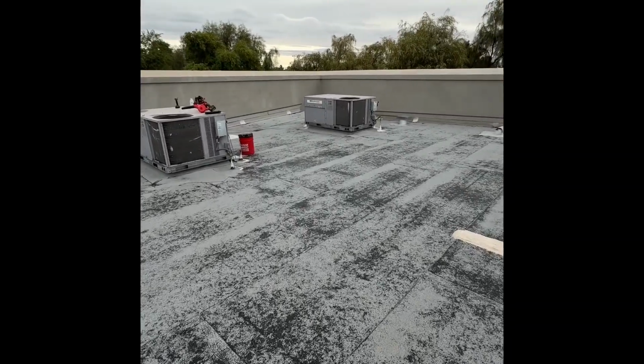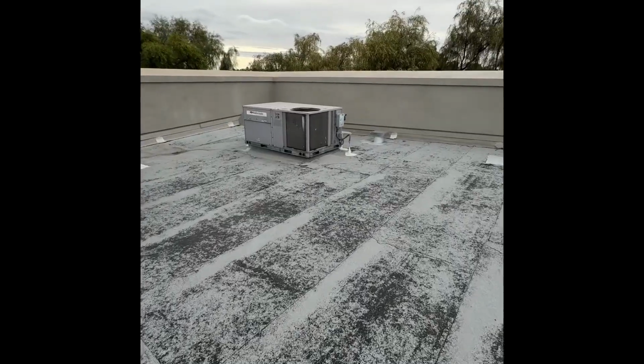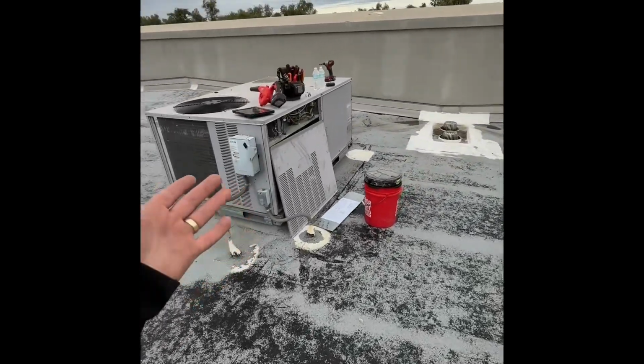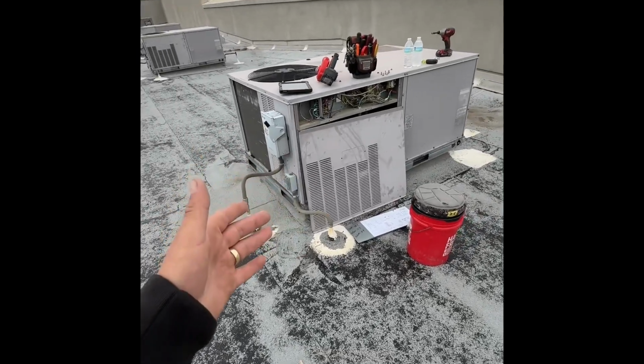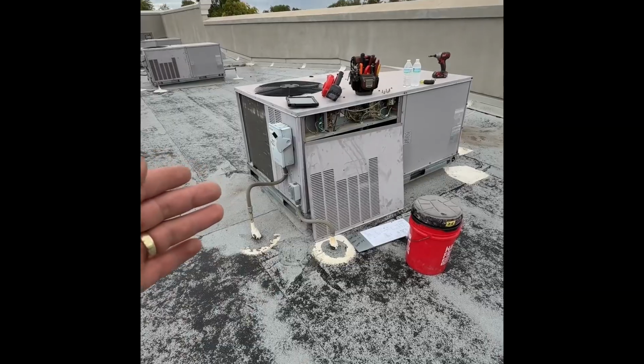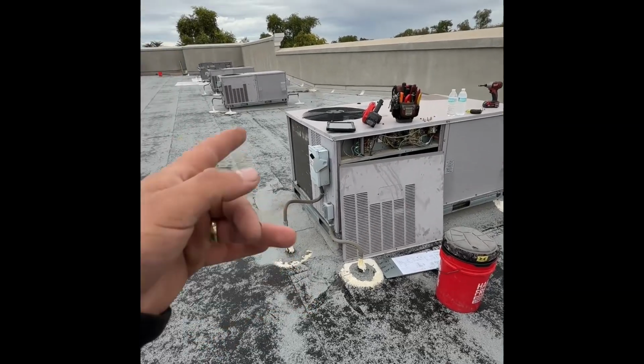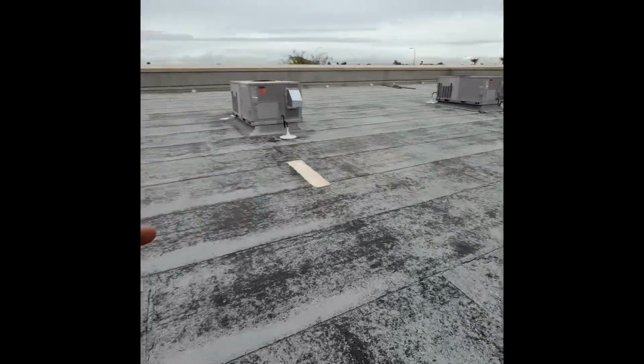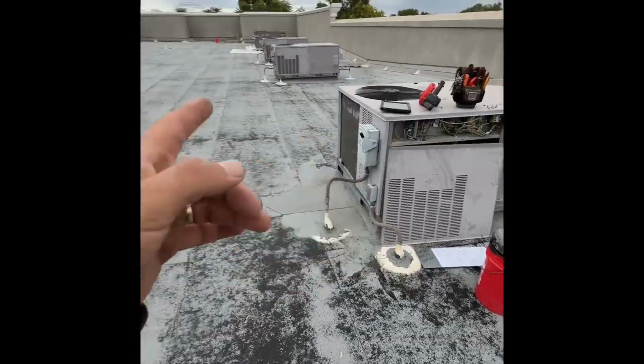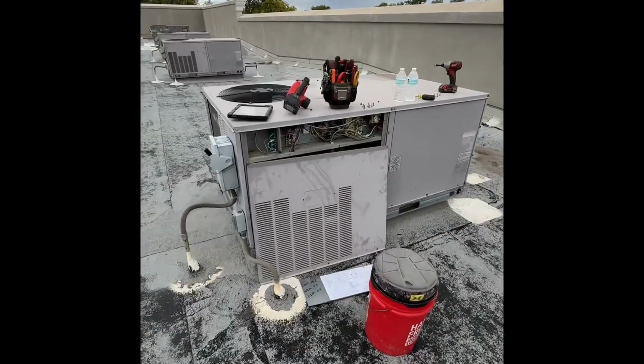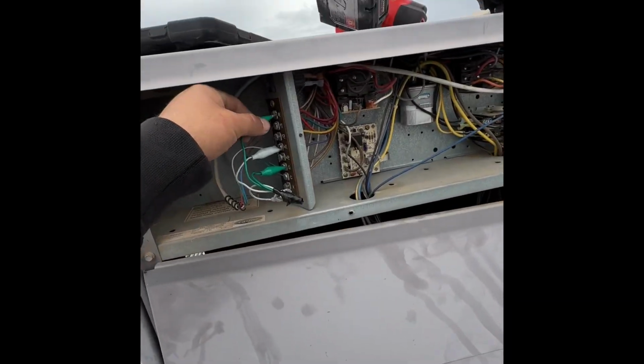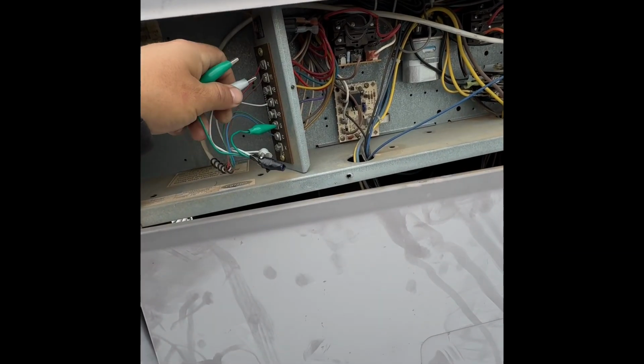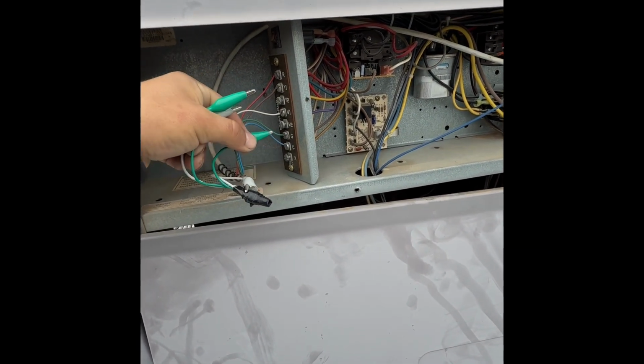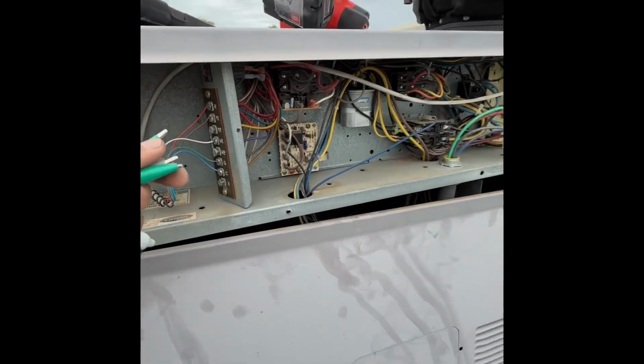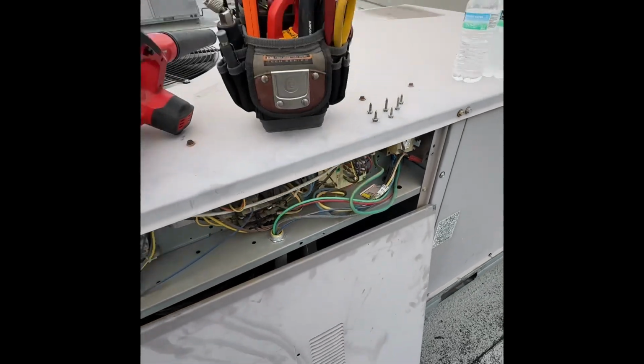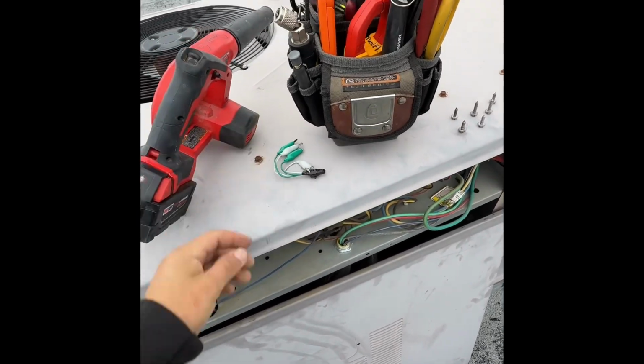So this is for you newbies that are into commercial or wanting to get into commercial or thinking about getting into commercial. This is how your manager, your company per se, would expect you to do a full commercial HVAC PM, washing coils, changing filters, and all these 8 units to myself, checking them door to door to door. And yeah, it could be really easy as long as you know the tricks and how to do it. Very carefully take these off too. You don't want to pop your transformer, and usually start on the red because that's tied directly to your transformer. Save that bad boy, because you don't want to make a oopsie and have to give them a free transformer because you messed up.